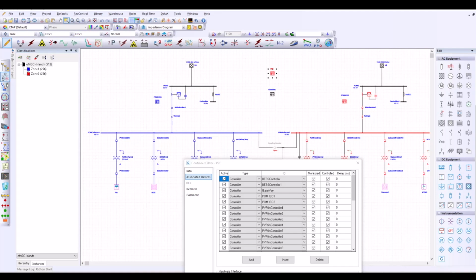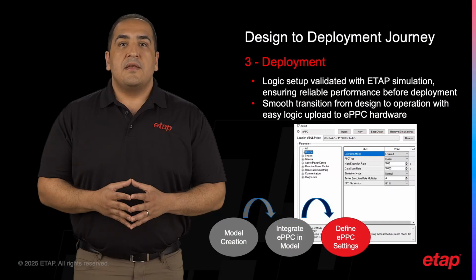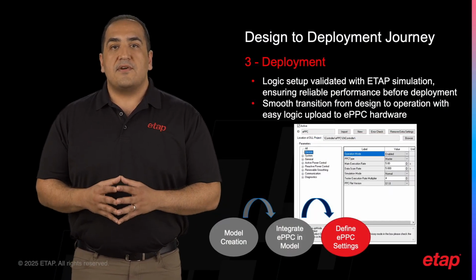In the Associated Devices page of EPPC, we should enable Monitor if EPPC reads the measurement from a certain device, and we should enable the Control checkbox if EPPC is supposed to send commands to that device. These options are particularly important for hardware in the loop or HIL testing and field deployment, where toggling these settings affects IO DNP3 tag assignment. And with that, we basically integrate the EPPC model into our model. It's very straightforward. The next step is setting up the necessary logic in EPPC.